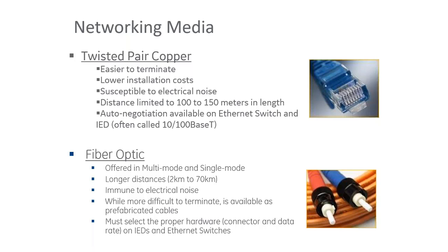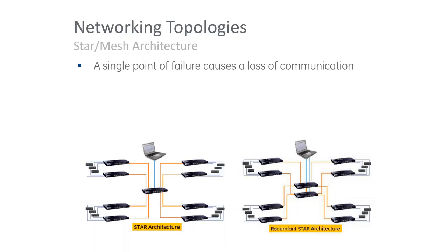When we talk about Ethernet, we also need to talk about topologies. The first is the star architecture — the most basic type, where devices connect into a switch, which then connects to a maintenance computer or SCADA system. The disadvantage is a single point of failure can cause a loss of communication. There is a way to make this redundant by creating a redundant star architecture.